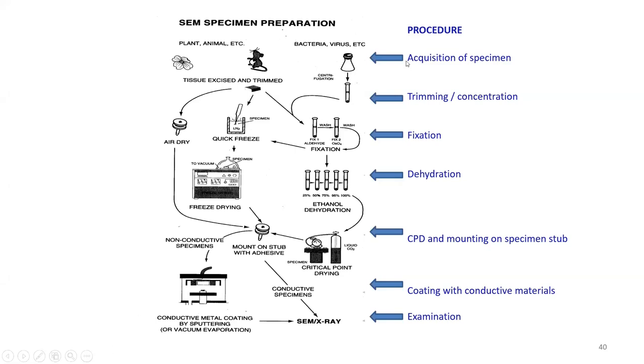Okay, so typically this is the flow of how things work for specimen preparation for SEM. If you're working with a powder sample, like for formulations, dry formulations or APIs like we do sometimes, you just simply take the powder, do a sputter coating, that is coating with a conductive metal, and go ahead and observe under the microscope. But typically for biological SEM, if you're working with cells, tissues and things like that, you have to follow an elaborate method, which is again not as demanding as TEM, because here you only want to preserve the surface features of your specimen.